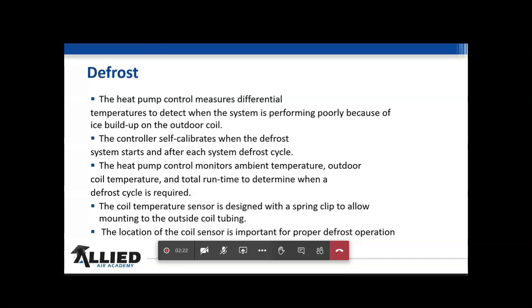The heat pump control monitors ambient temperature, outdoor coil temperature, and total run time to determine when a defrost cycle is required. And these things have a lot more meat to them in just a few moments. The coil temperature sensor is designed with a spring clip, and it's going to be hooked to the outdoor coil tubing. What's not written here, it's imperative that if you have to replace them or anything of that nature, you put them back where they belong. Usually on the 2 and the 3 tons, they are 12 rows up. And on the 4 and 5 ton, they're going to be about 24 rows up. If you start moving those sensors in any way, shape, or form, it can throw the whole thing off, and you'll see why in just a few minutes. And that's why the location is really important for this.